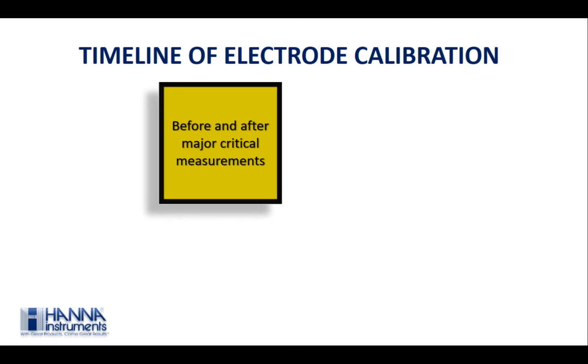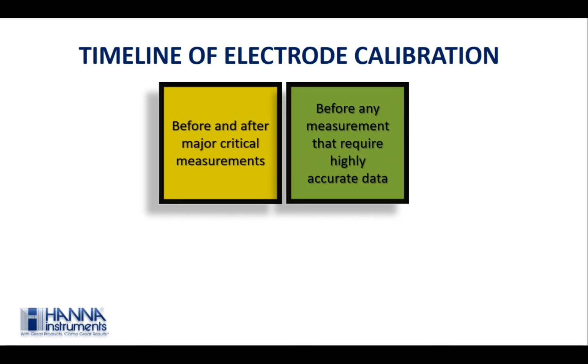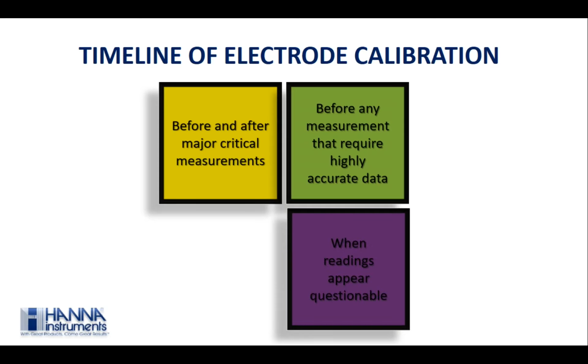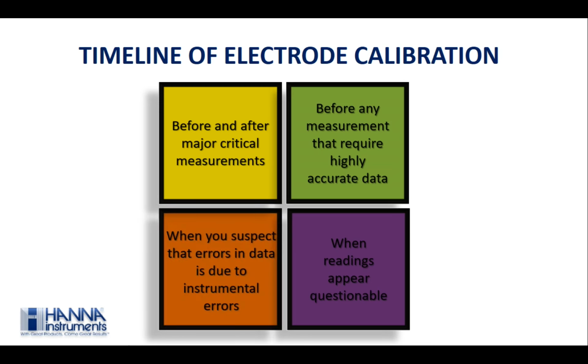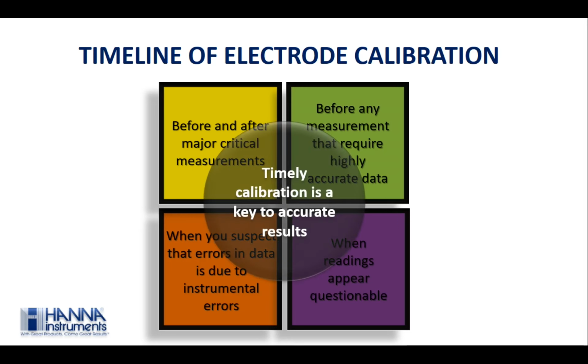And after ending your measurement, you will understand if there is any drop in slope or offset due to sample reaction in the electrode. Other than this, one could calibrate before and after critical measurements that need to yield highly accurate results. Calibrate when you think that the readings are not accurate or suspect any errors in the meter, sample or electrode. Calibration is necessary when readings appear erratic. Thus, calibration is the key to yield accurate results.